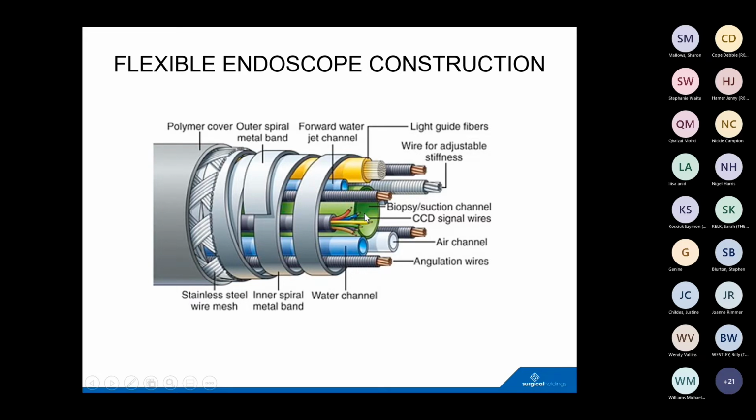And the first point in terms of potential damage: if you get fluid ingress into this internal structure of the instrument, it can cause a lot of damage, potentially very expensive damage. And that could be, for example, fluid ingress due to a problem with the bending section, so there's a hole in the bending section rubber, or it may be internal.